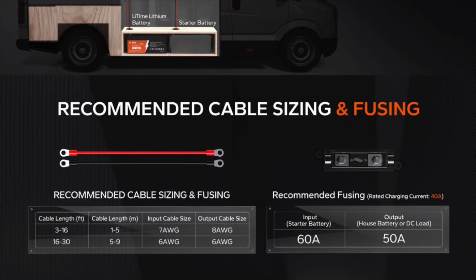Now, did I need to run 6-gauge wire because I'm running 20 amps? Absolutely not. But if you read the manual, it recommends 6-gauge wire for 40 amps over about 10 feet or so. Definitely follow the manufacturer's recommendations and be careful with things. That's why I also put in inline circuit breakers. If this was running at 40 amps, you'd want to put a 60 in there - that's what I ran, 60 amp. The other one has, I believe, an 80 amp on it. Basically, you only want to run about 80% of your load for the breaker size. Size up your breaker - don't run, say, a 40 if you're running 40 amps. Run about 10-20% more so you've got some leeway.